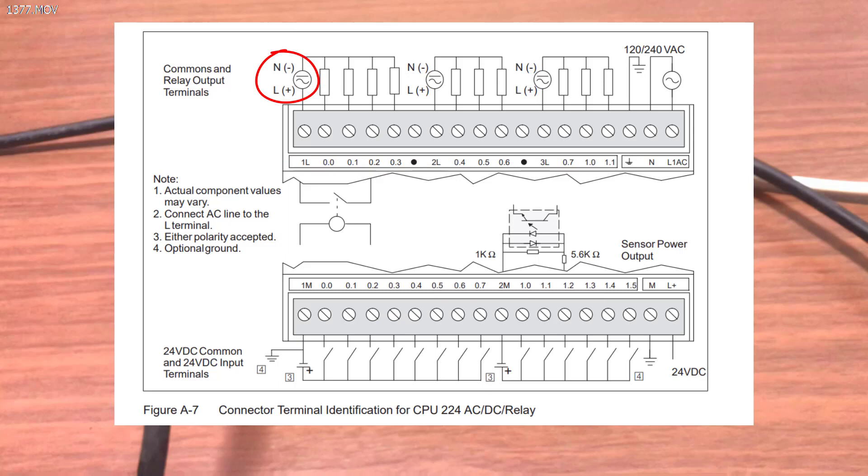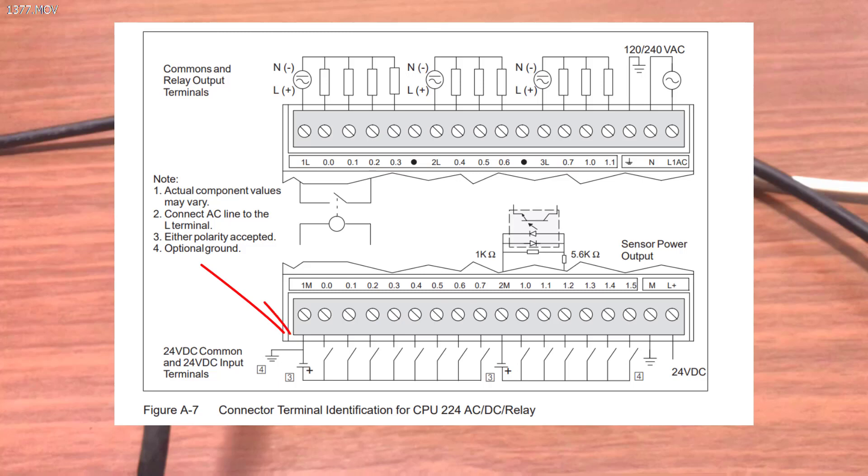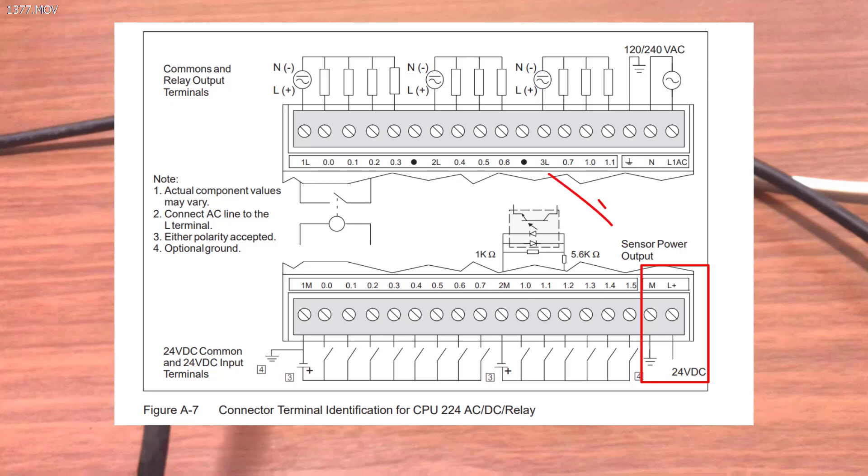And when we look at our input, we can see that we need to apply negative volts at 1M and then 2M. And we can take this source voltage from our internal power supply which is labeled as the sensor power supply M and then positive L, which is 24 volt supply internally from the system.